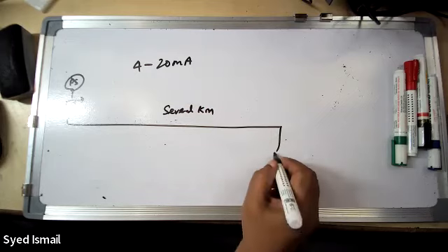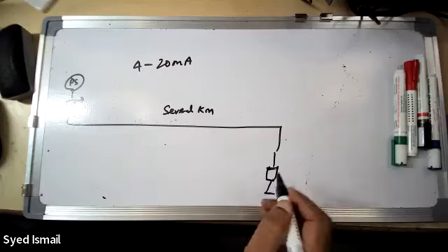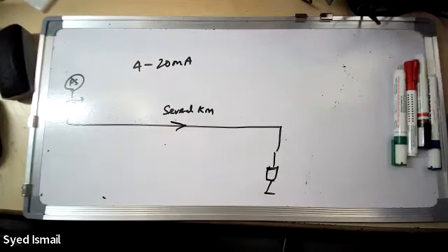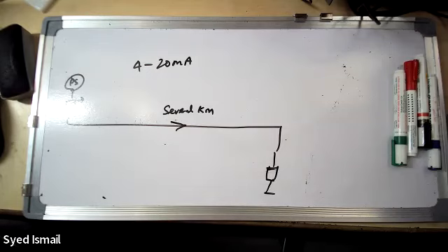And then here is grounded, for example. So I measure, here I put something else and measure whatever may be. What it guarantees here is the current that is flowing, which will vary between 4 to 20 milliamperes. You cannot transmit voltages over long distances with long wires, because we know already the wire has resistance, which means it will reduce the voltage.